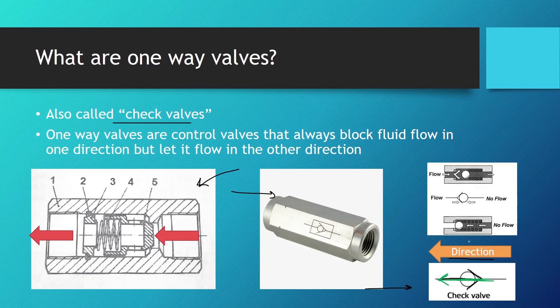These valves consist usually of a spring which pushes the closing element, obstructing flow in one direction. They can also push the closing element by using their own weight and the counter pressure coming from the other side. The fluid pressure pushes the little ball to the right, opens up the pathway, and lets fluid flow from left to right — opposite from the arrow. There is no flow from right to left, but we have flow from left to right.